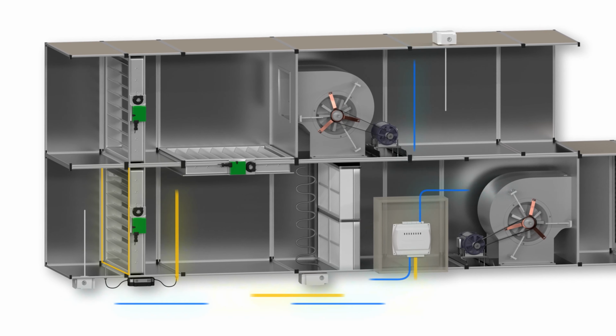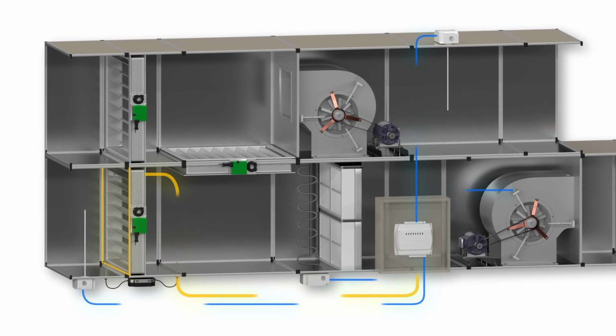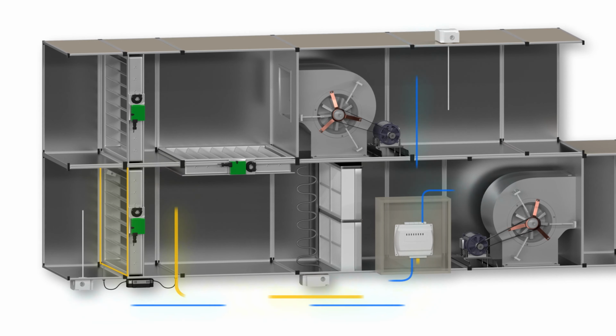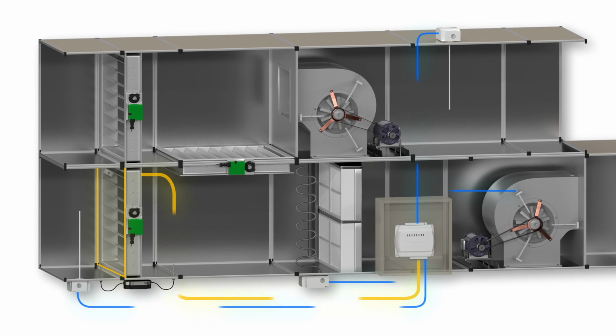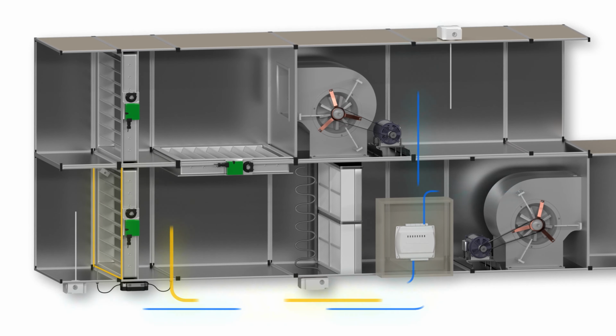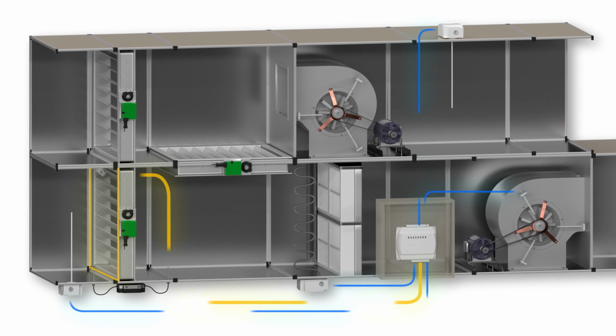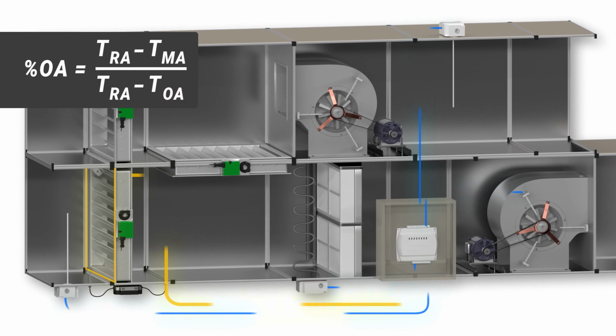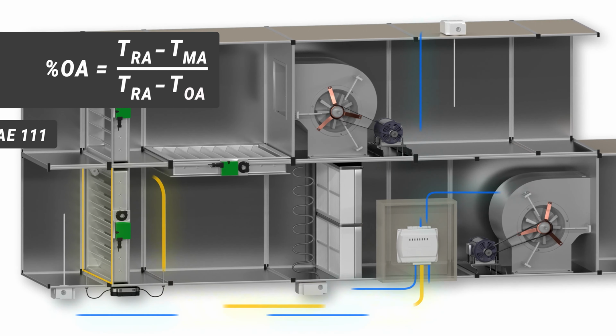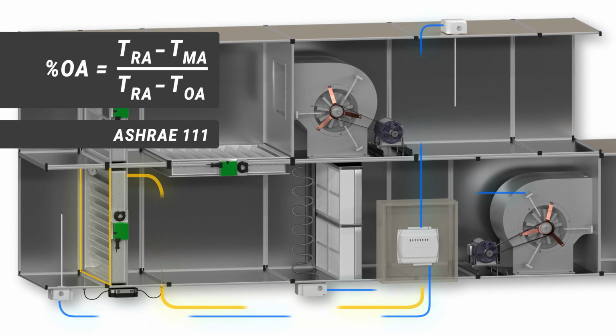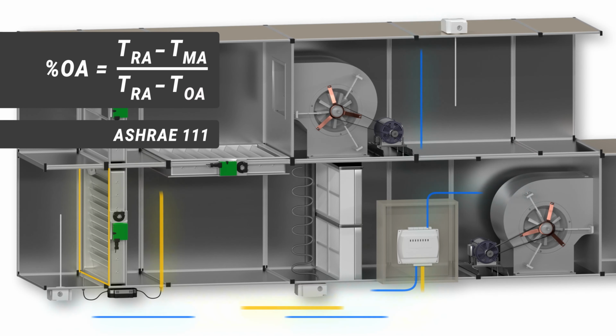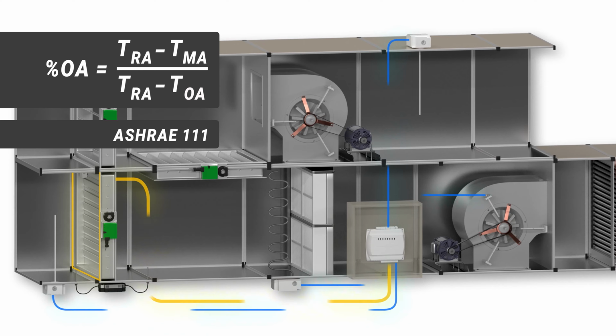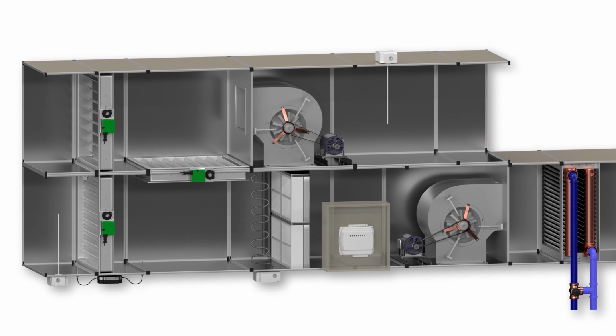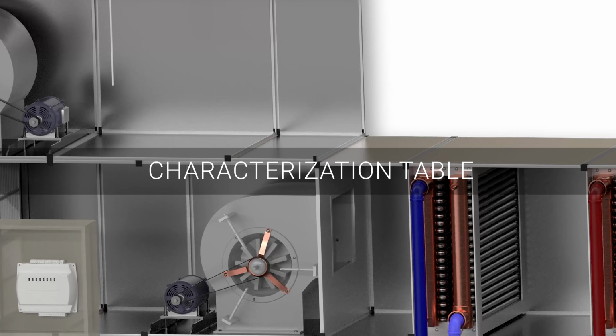During Learn Mode, the mixed air damper assembly is positioned gradually through its full mechanical span, as measured by the inclinometer. At each position, sensor readings are allowed to stabilize before they are sampled and averaged. Leveraging the temperature ratio equation, found in ASHRAE 111, these readings allow the AFMS to calculate the fraction of outside air that is delivered at each position. The results are recorded in the characterization table.